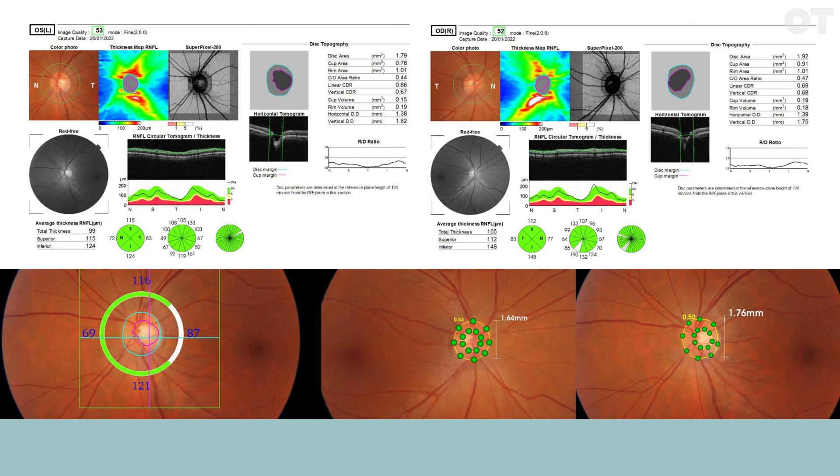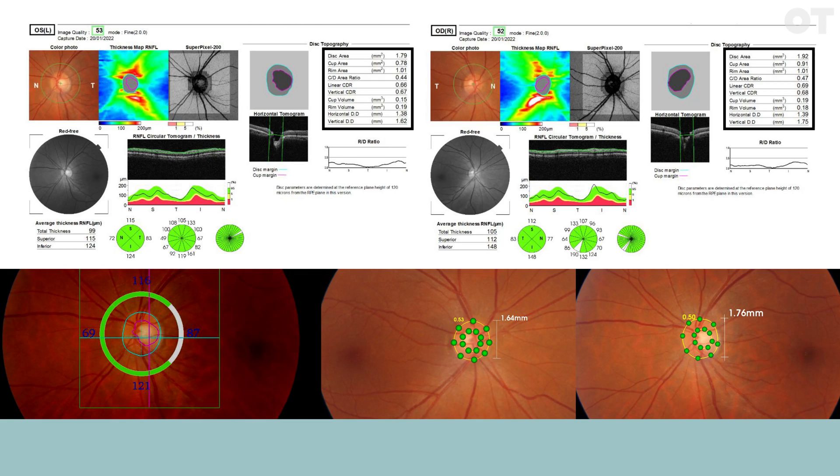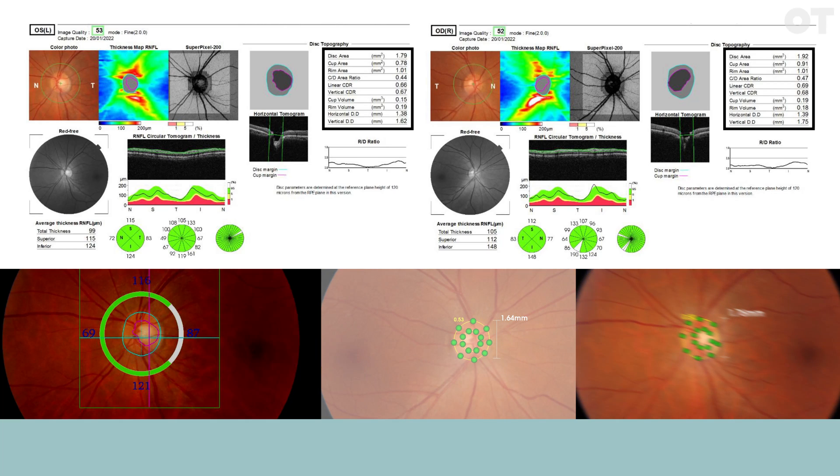An OCT or optical coherence tomographer can measure disc size and calculate CD ratios for you. This is fairly accurate but be aware that different manufacturers' machines may give you different values. You do need to assess the image for yourself to ensure the instrument has determined the boundaries sensibly. It can misjudge it if the view were impeded by a small pupil or media opacities or if the patient moved a lot.